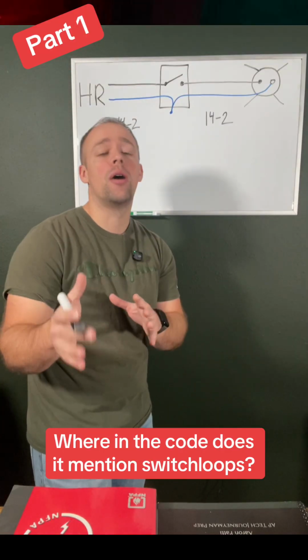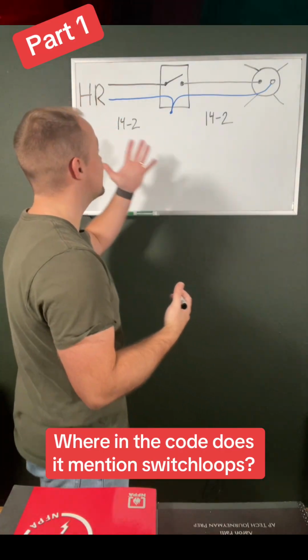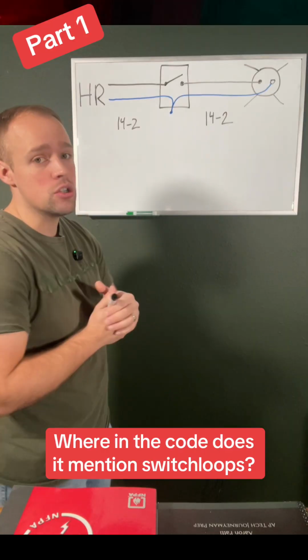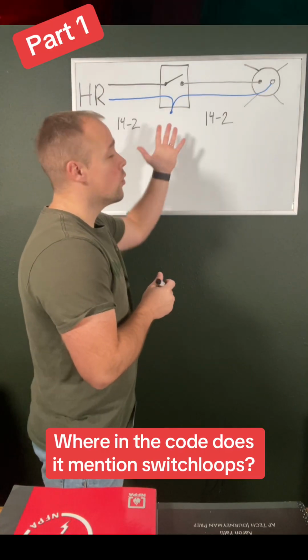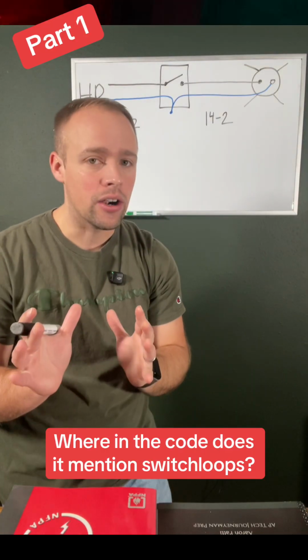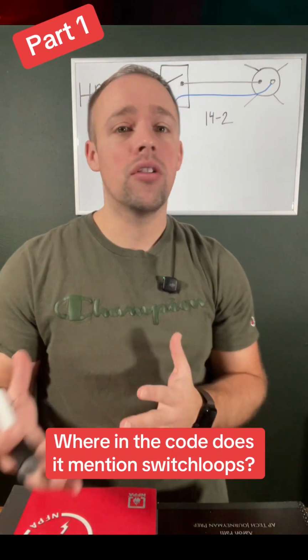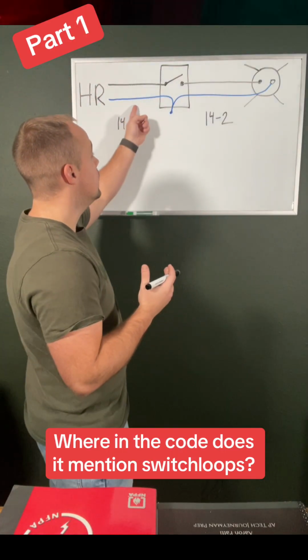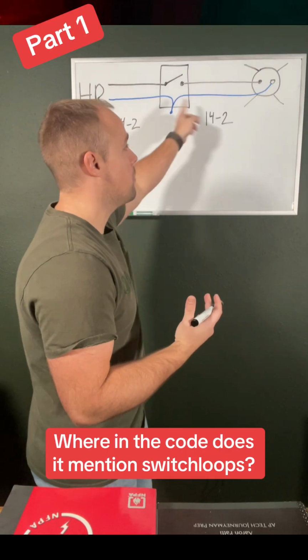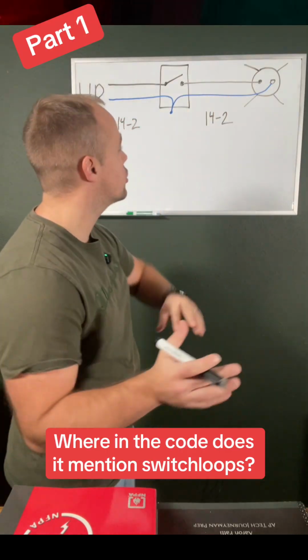But first, I want to talk about wiring a regular switch to a light. In this instance, we have a home run with 14-2 cable. And as you can see, it goes to the switch box. And let's be clear, a switch does not utilize the neutral. Okay, so that's why our neutral just gets spliced to a wire nut and then it passes through to the light. But let's talk about the ungrounded conductor.